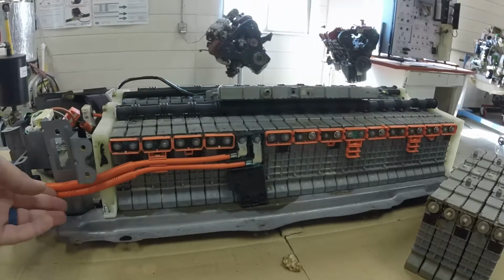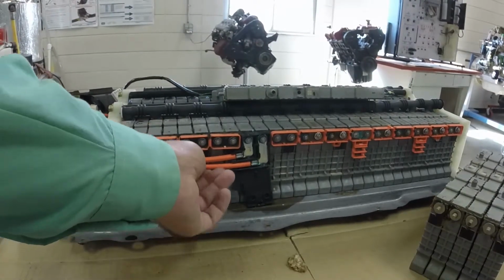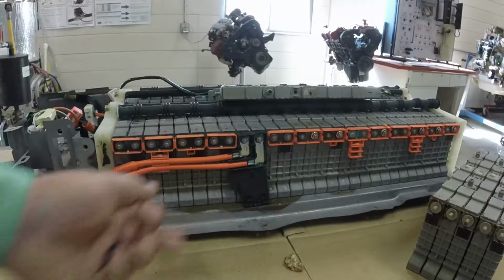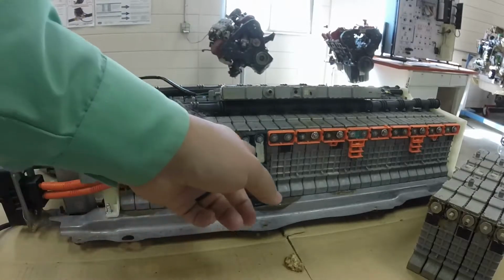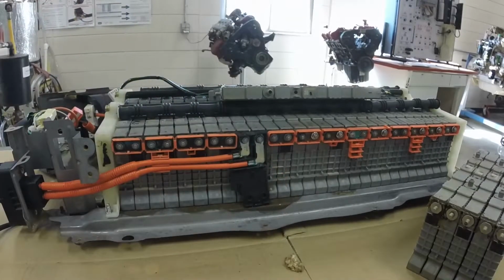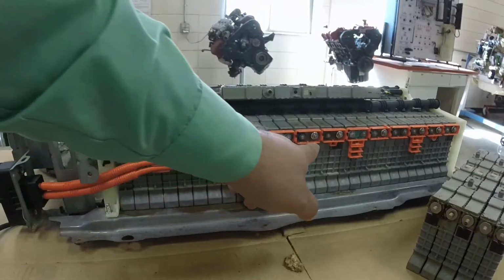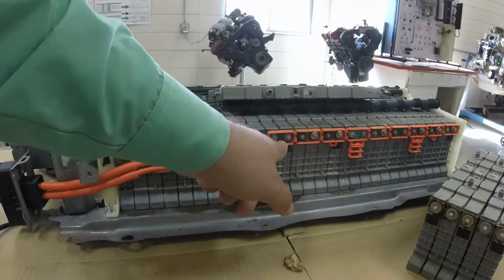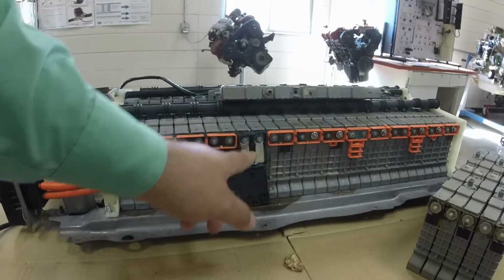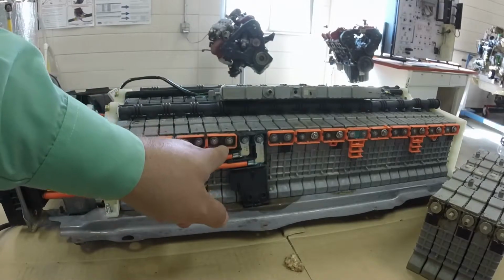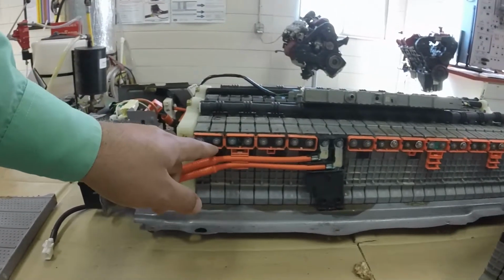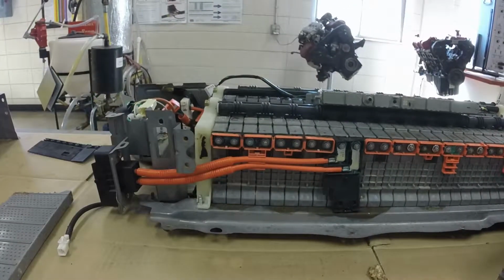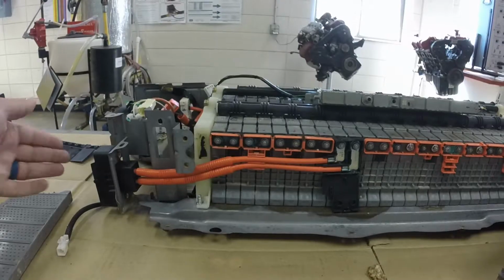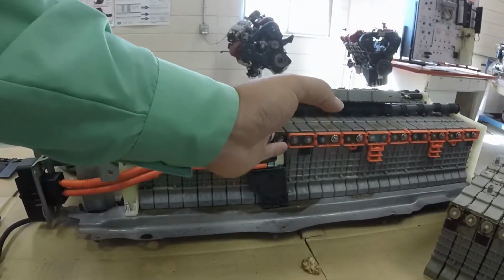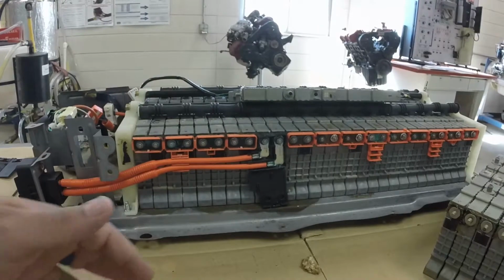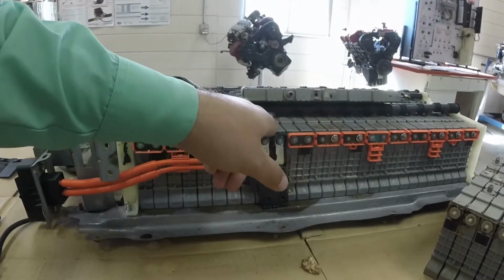If we look in here, we have a couple of heavy gauge cables, about 4 gauge, and these come to two of these battery modules. If you follow the sequence of the bus bars, we have bus bars on these two, the two terminals for these wires here, and then again bus bars here, here, here, and here. This high voltage disconnect actually chops this battery in half, disconnecting between these two modules.